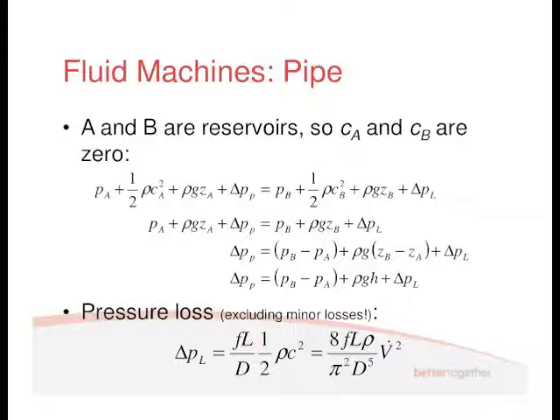And so what I've done is I've rearranged the equation. I've taken out the dynamic pressures. And so I've still got the PA term and the PB term. I've got my hydrostatic pressures, ZA and ZB. And I've got my pressure rise due to the pump and the pressure loss due to the pipe system, due to friction and minor losses. So I can rearrange this equation, grouping the static pressures on one side and the hydrostatic pressures on one side. So there's my PB minus PA and ZB minus ZA. Notice that the difference in elevation is going to be the height difference, so we can often replace that with H. And the difference in static pressures, obviously if they're open reservoirs, the difference in static pressures is zero. But we don't know that in this situation, so we've assumed that they're still there.